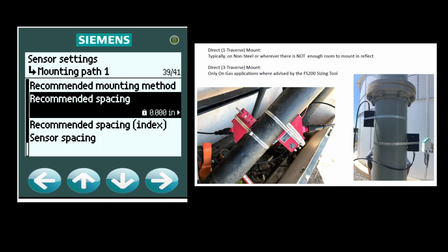By the way, if you're using the mount location on a vertical pipe, it needs to be upward flowing liquid or gas rather than downward. More so for liquid than gas. If this is a horizontal running pipe, then you want to stay somewhere on the sides, typically anywhere between the range of 10 o'clock and 2 o'clock.